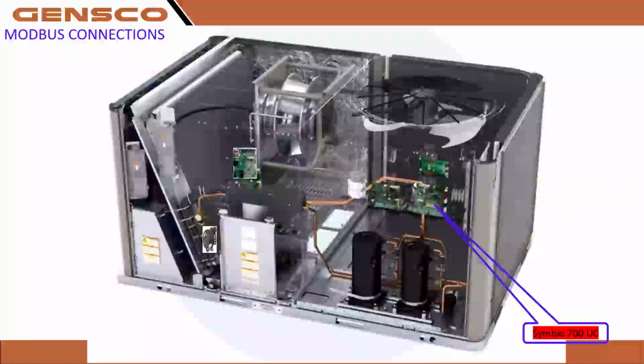Modbus. Here's our Symbio 700. Modbus is going to hop up to the adapter board through this hinge. Again, I want you to check when we open up this hinge, just verify that you have nothing hanging there that doesn't have a designated space. If you get used to looking for that the first time you start up, it might save you a bunch of time. If you do find any factory issue that you think is factory, please, please, please take a picture of it with the data plate and send it to tech services so we can report that to the factory as soon as possible. That way we can let them know that's what's happening in the field or transport, and they can fix it, hopefully.